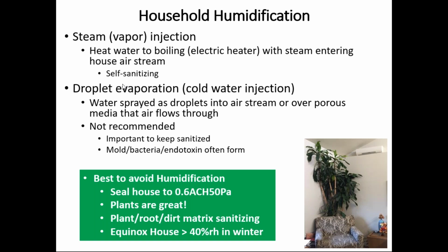Now, with steam vapor injection, all of the energy needed to vaporize water, it takes about 2/3 of a kilowatt hour to take liquid water and turn it into vapor. That's an inefficient process. It'd be much better to vaporize that water with a heat pump and get maybe a 3-to-1 return on your electric energy. Cold water injection or droplet evaporation is, in effect, if you are heating your home with a heat pump, getting that 3-to-1 energy benefit in vaporizing water, but it comes with some problems.